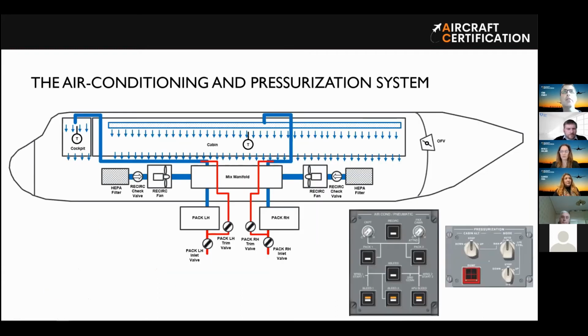Here you have a schematic of the air conditioning system. So you can see here is the PACK and here is the bypass. Both PACKs are connected to a mix manifold. And then you can ask yourselves, how is the humidity controlled? Well, humidity normally is controlled by recirculation.